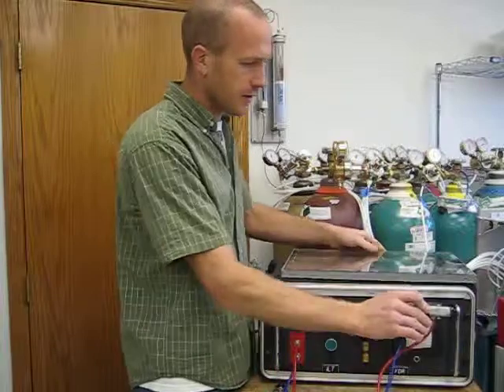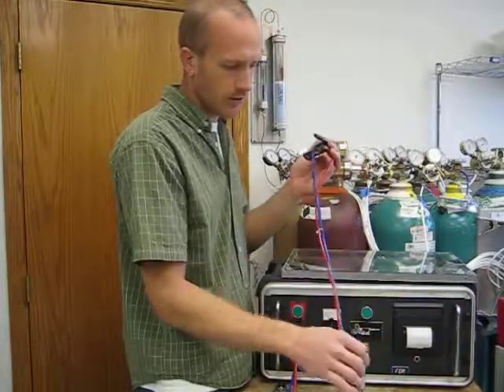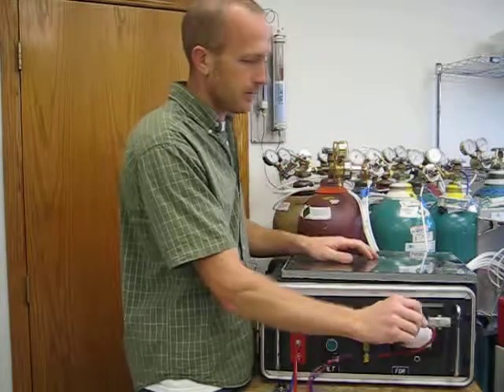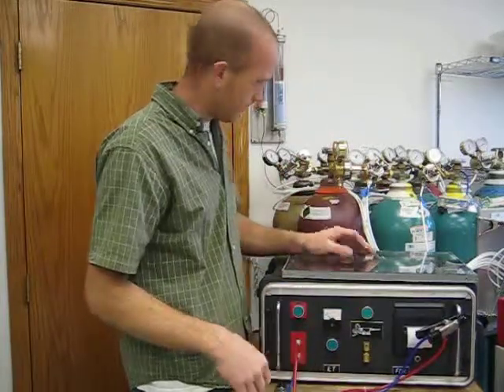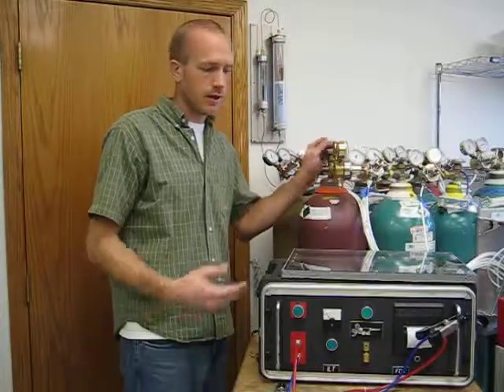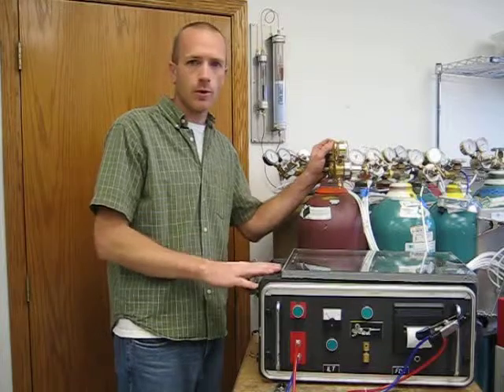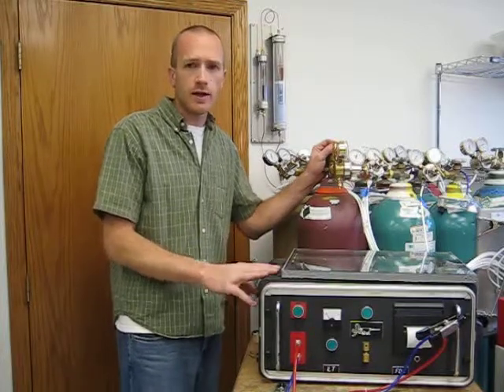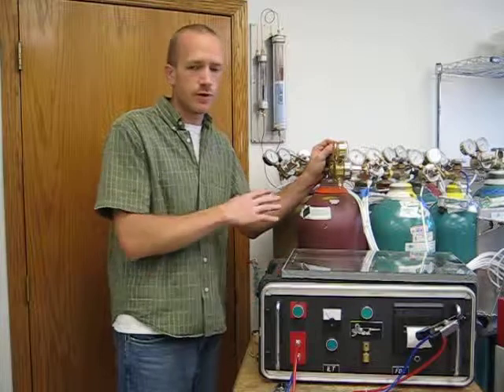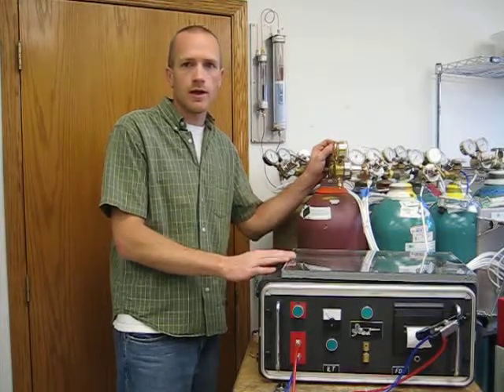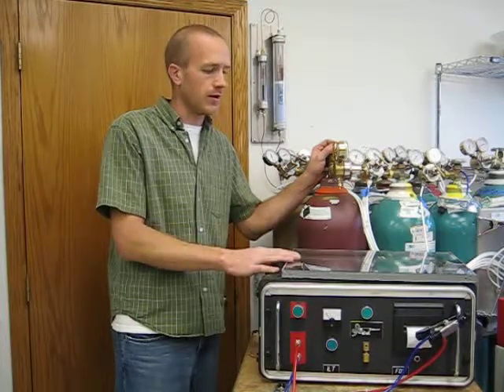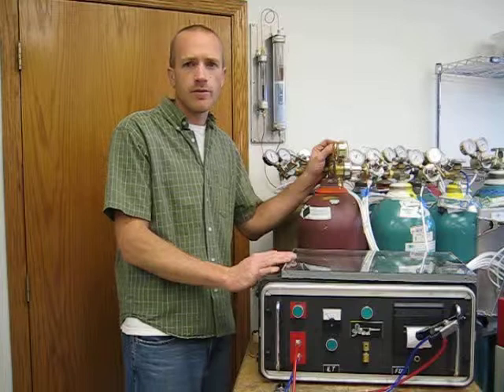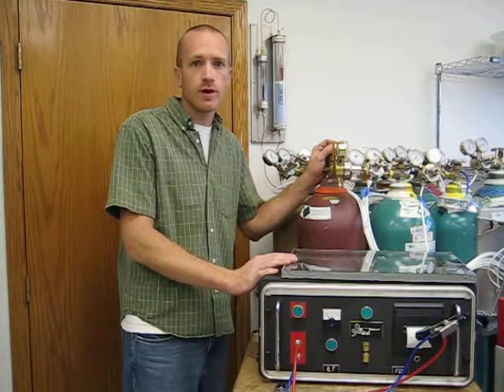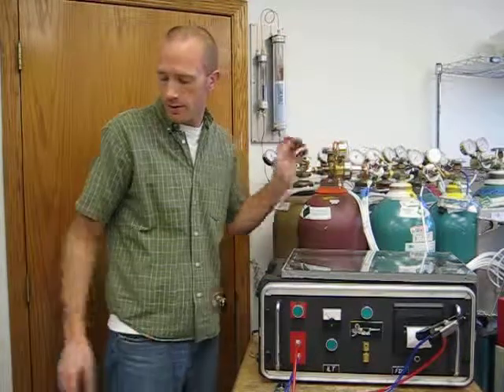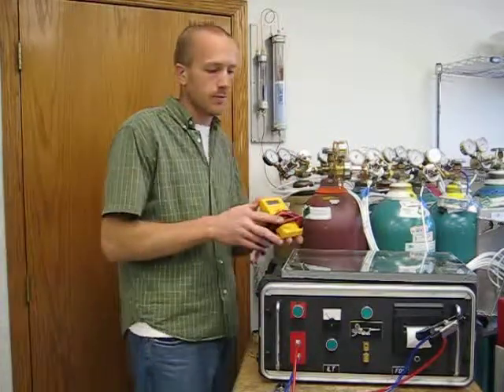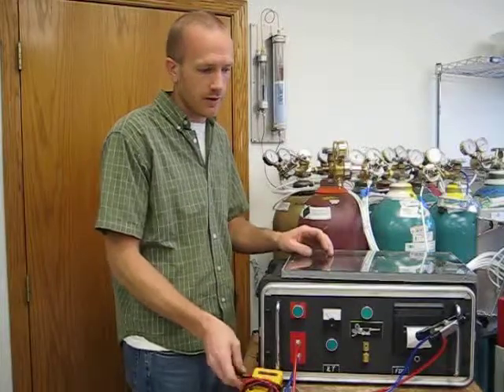The machines from us include the lances and hoses for either one or two hole filling method, or testing method I should say. The machine will also include bottle regulators, so you can connect the argon or krypton to the machine. The machine doesn't have to be continually hooked up to the gas. It's just for calibrating the machine. So once you're done calibrating it, you can disconnect the bottle, turn it off. Calibration takes about 5 minutes, maybe 10 minutes if you haven't done it before. It's really a simple process. The machine also includes a voltmeter, so you can do the calibration, and all that is included in the price.